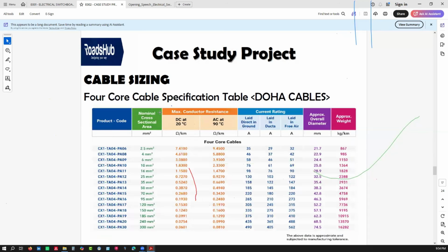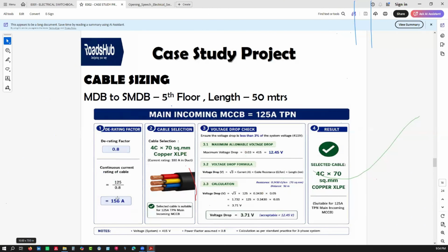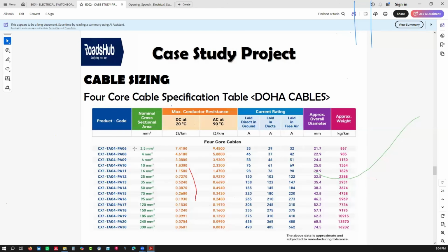So if you're working with 156, remember, if you go to this cable size table, I don't see any current that is going to be laid on a duct with 156. So I have 145, but we cannot go lower. So I go for 180. So when I check the cable for 180, it's a 70 mm squared.